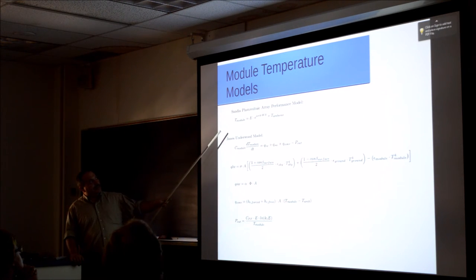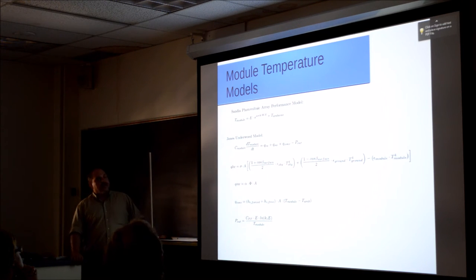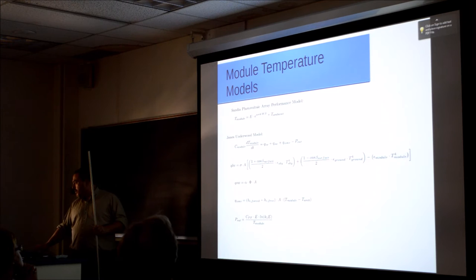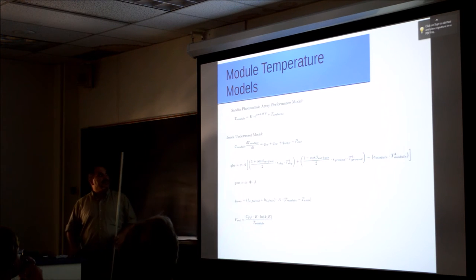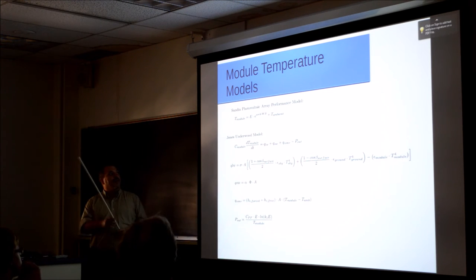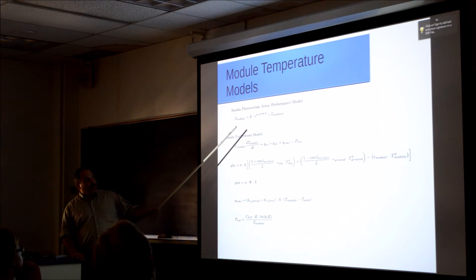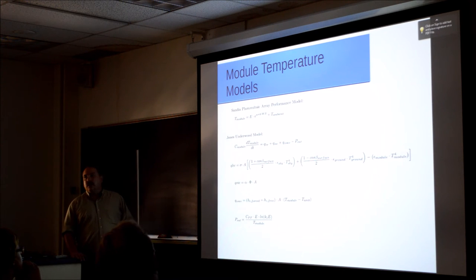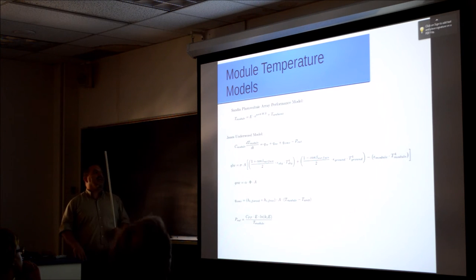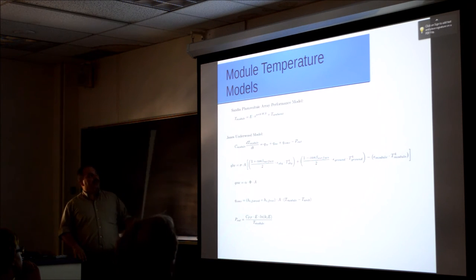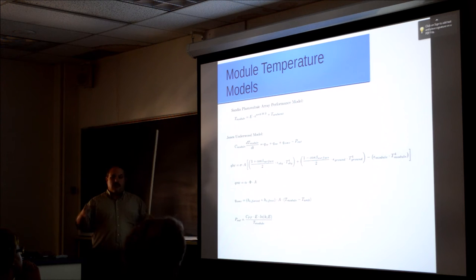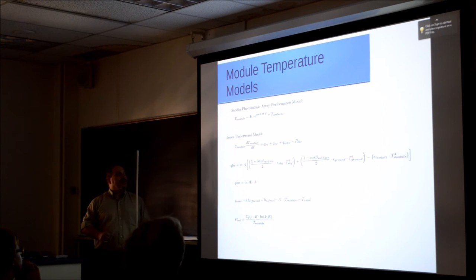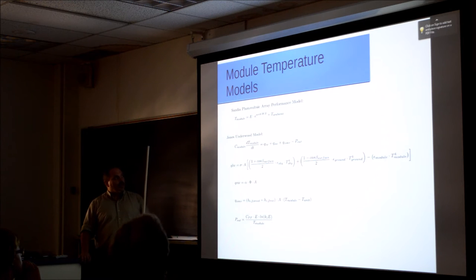The steady state model, because it's dependent very heavily on irradiance, ends up making huge spikes as irradiance changes — for example, if you have cloud cover coming by. That's fine over a long term. If you're looking at output over say a year and you're trying to predict roughly what you're going to get out of this, that's going to give you a fairly good number. But if you're trying to look at something on a shorter time scale, that's going to end up being way off.